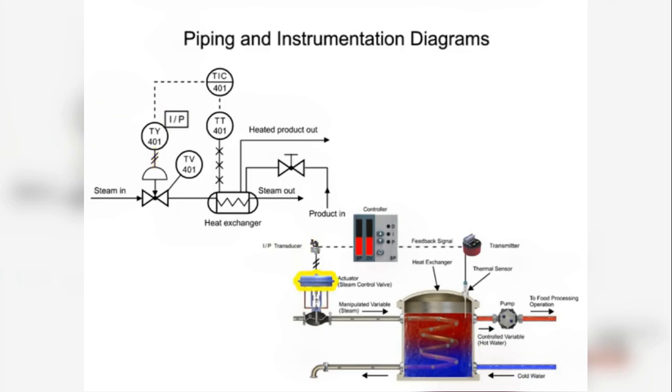The pneumatic-controlled diaphragm actuator that opens and closes the globe valve regulates steam in the process. The actuator is represented by the half-circle in the P and ID. The arrow pointing downwards from the actuator indicates a fail-closed valve type.